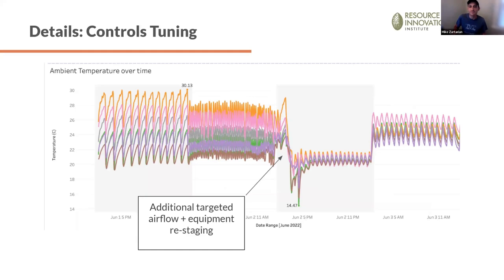After we've debugged all the big stuff and we're getting into tuning, this is where we can really make a huge difference. This room has, I believe, 4 HVAC units and 2 or 3 dehumidifiers, and they weren't staged in the control system. They all just came on and then all turned off, creating a huge amount of variation in the room. You're seeing about a 10 degree Celsius, or 20 degree Fahrenheit, difference between one point in the room and another at the same time.